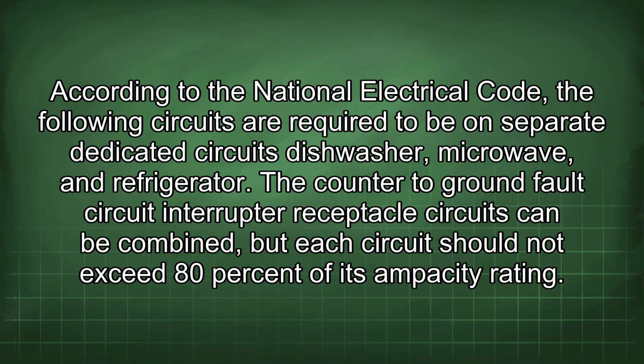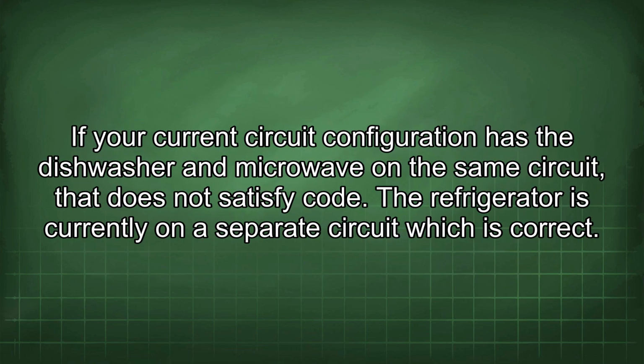According to the National Electrical Code, the following circuits are required to be on separate dedicated circuits: dishwasher, microwave, and refrigerator. The counter ground fault circuit interrupter receptacle circuits can be combined, but each circuit should not exceed 80% of its ampacity rating. If your current circuit configuration has the dishwasher and microwave on the same circuit, that does not satisfy code. The refrigerator is currently on a separate circuit, which is correct.